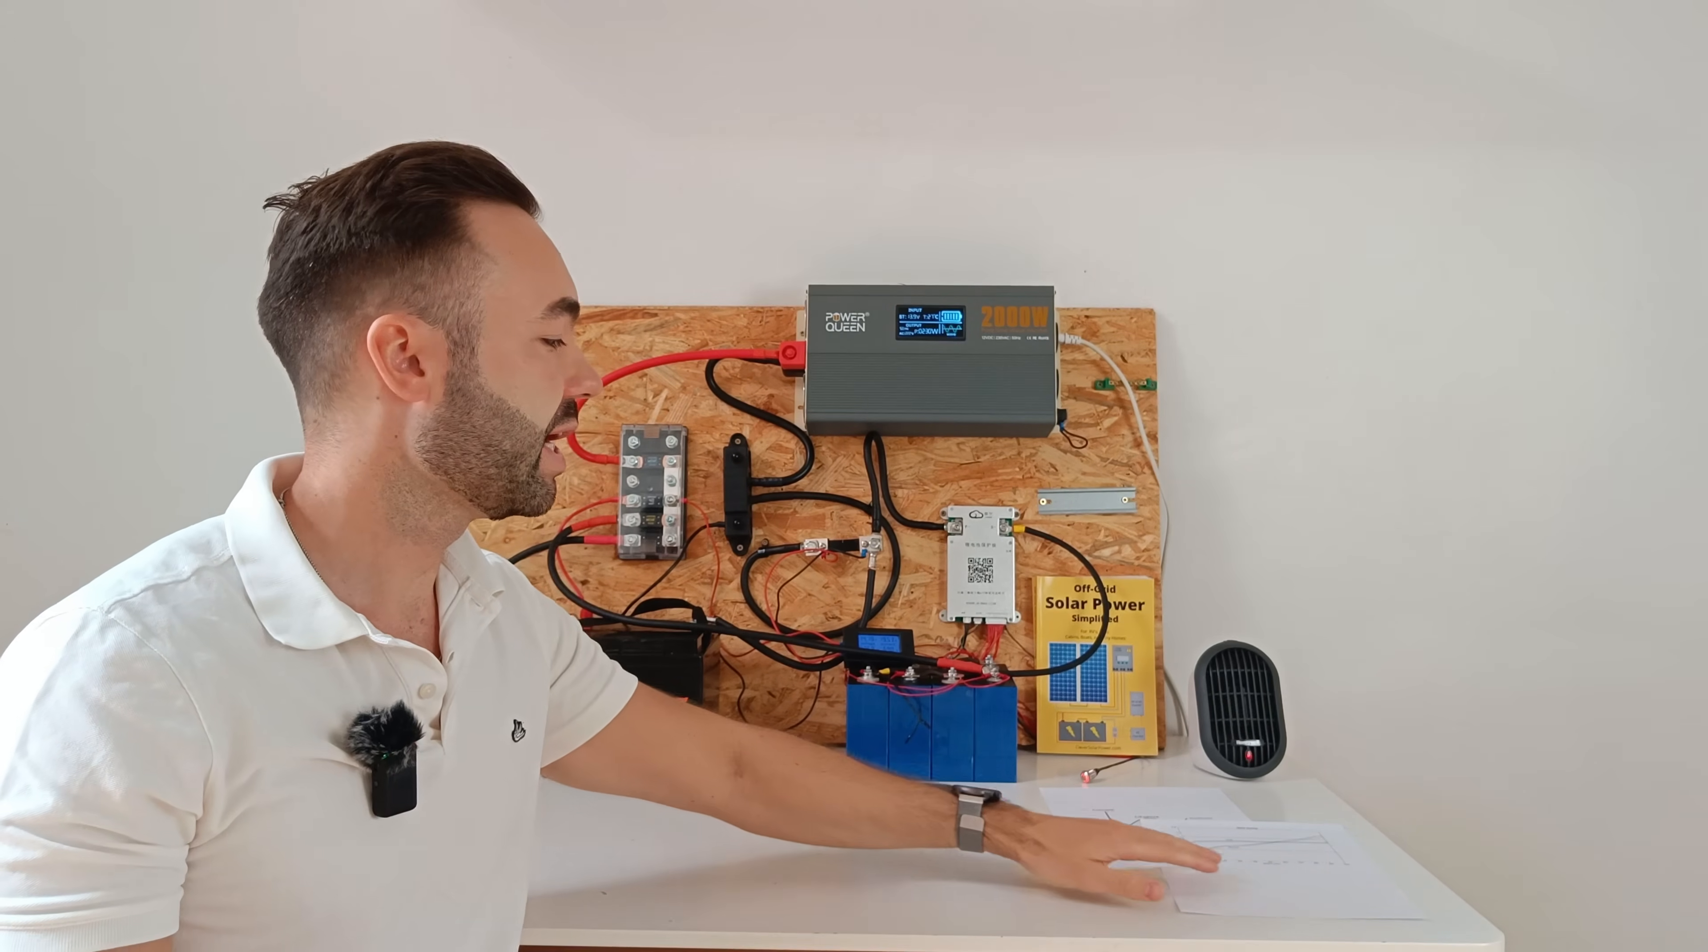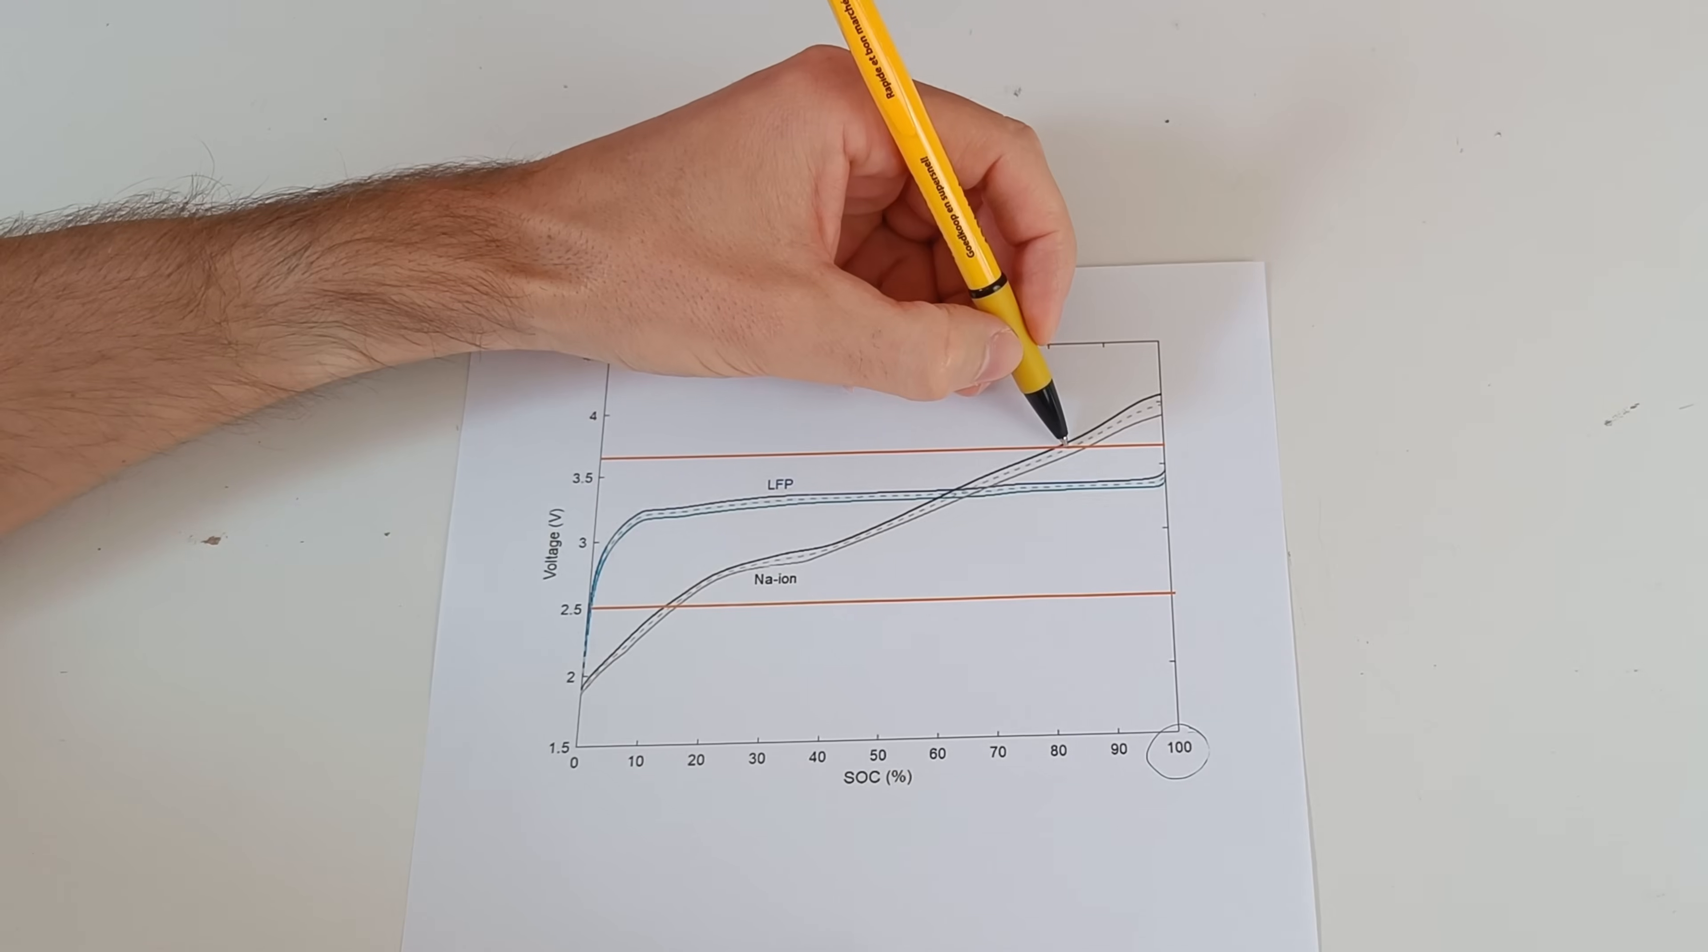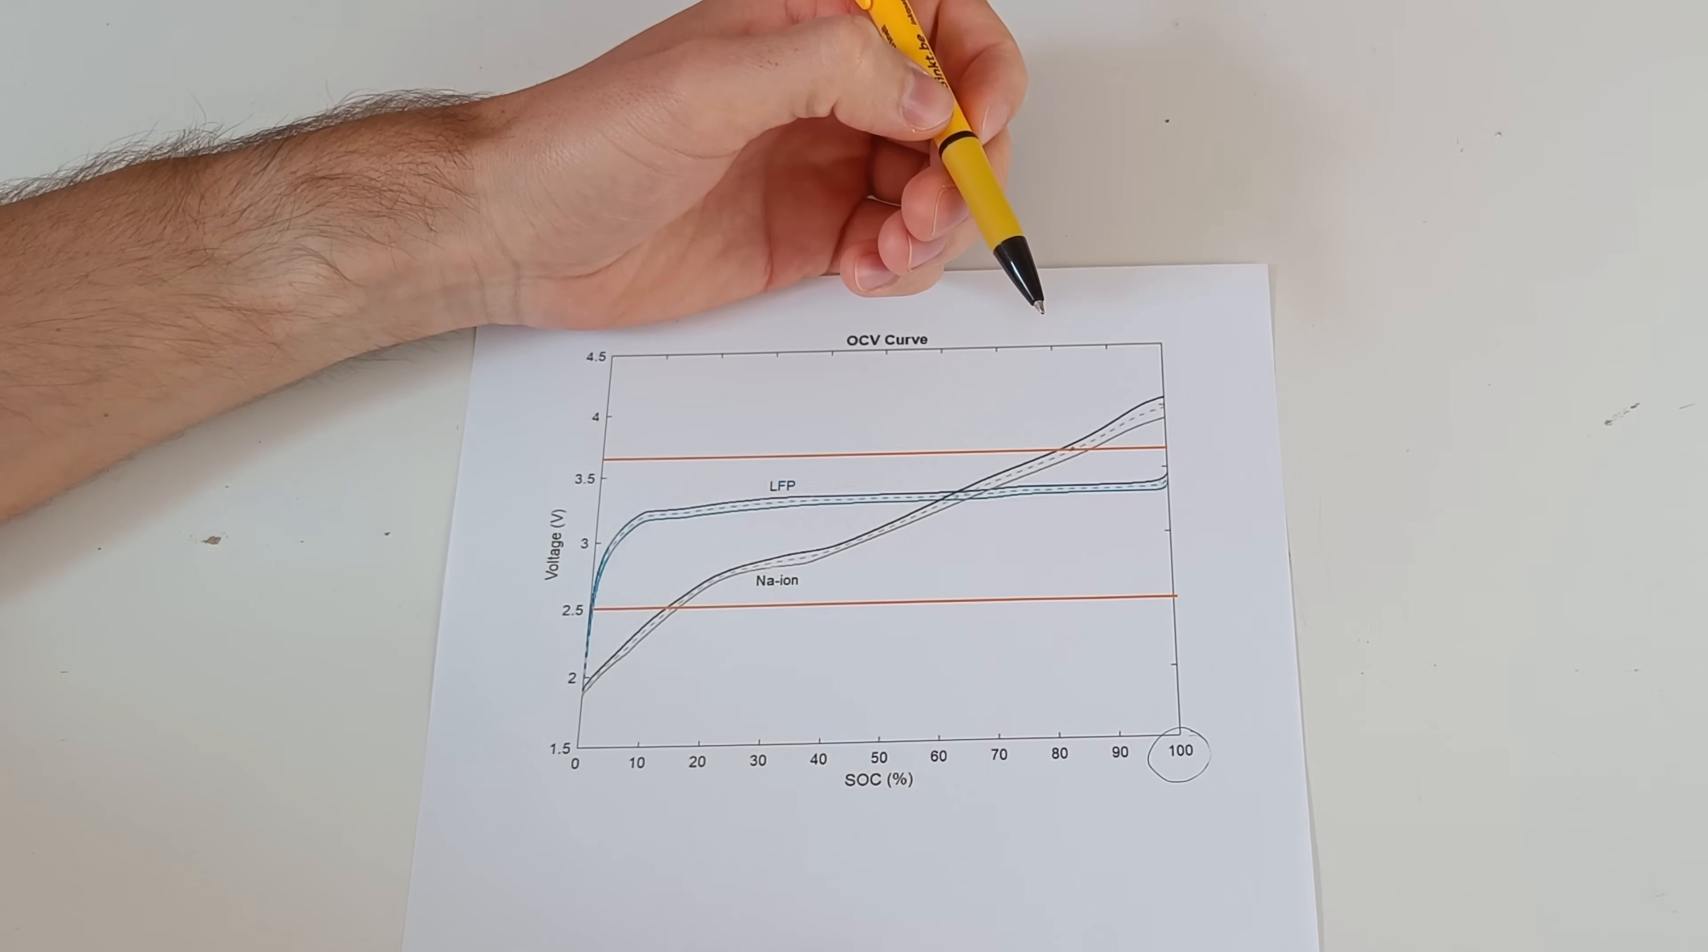So let's look at the graph again. In the beginning, when we are at 100% state of charge, the sodium has a higher open circuit voltage because lithium is resting at 14 volts. And the battery with the highest voltage delivers the current.